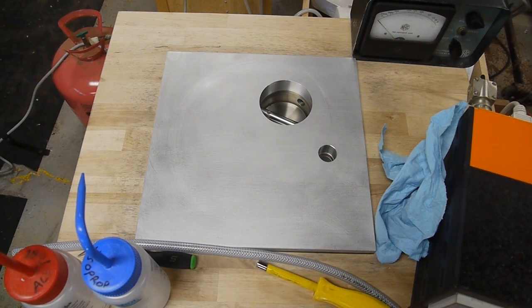The reason for this is that helium has a different thermal conductivity than nitrogen and oxygen do. When the helium enters the vacuum gauge it causes it to respond differently than it would to air even though the pressures might not actually be all that different. Also helium is able to permeate through many different materials and just get through very small spaces in general. So it's a good leak detector gas, in fact it's the best I think.